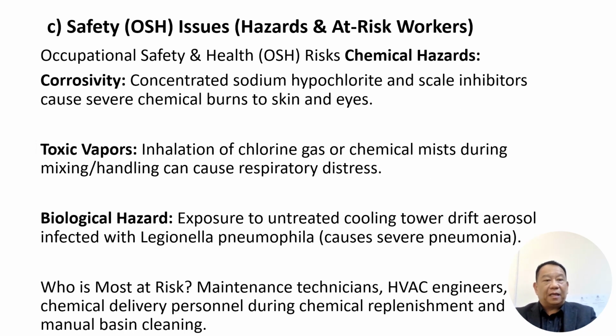Okay, the occupational safety and health issues and hazards for at-risk workers, right? The safety and health risk of this chemical hazard, number one, is corrosive. The concentrated sodium hypochlorite and scale inhibitor cause severe chemical burns to skin and eyes. Then toxic vapors: inhalation of chlorine gas or chemical mist during mixing and handling can cause respiratory distress. Therefore, it is compulsory to use a mask. And then a biological hazard: exposure to untreated cooling water drift aerosol infected with Legionella pneumophila, causing severe pneumonia. The at-risk people here are our maintenance technicians, the engineers and chemical delivery personnel during chemical replenishment and manual basin cleaning, right?